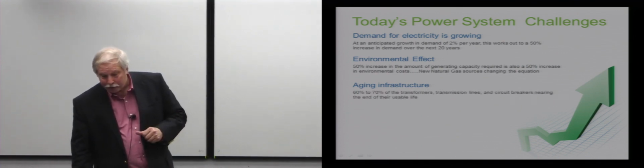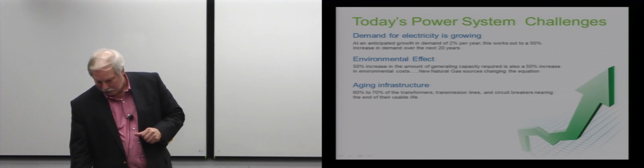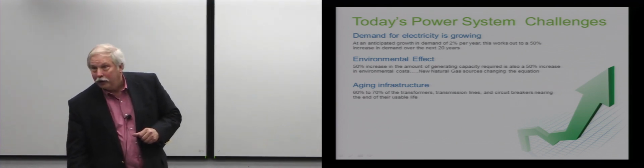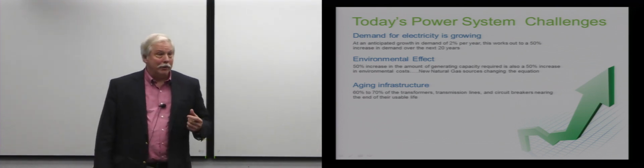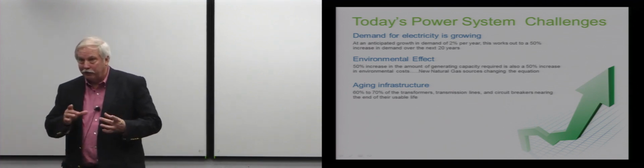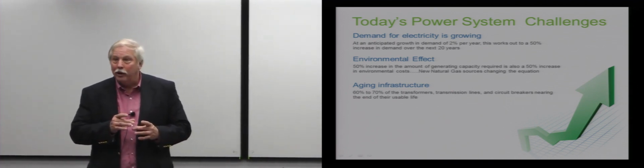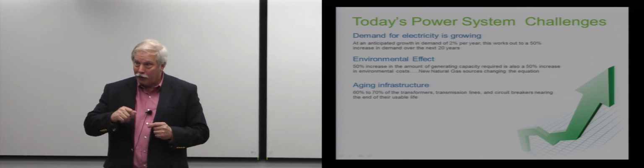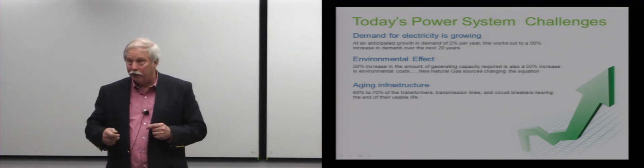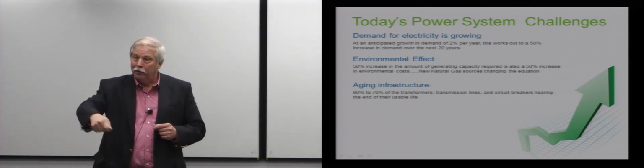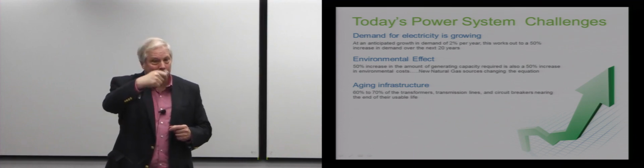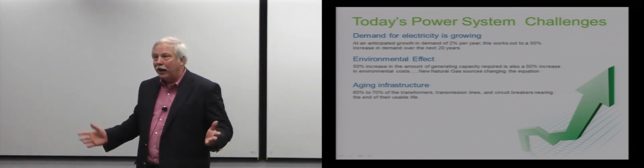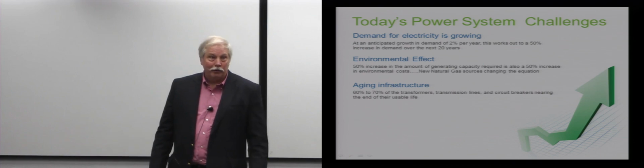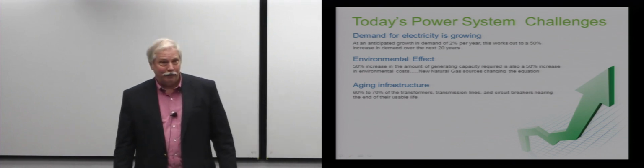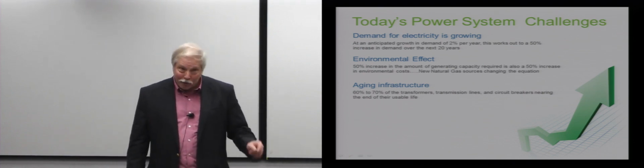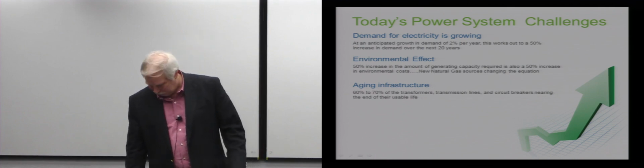60 to 70% of the transformers in this country are old. Transformers fail because of age. There's simple deterioration of insulation. All of the transformers built 30, 40 years ago are paper wound. Paper is cellulose-based, and cellulose decays over time. So they're all ticking time bombs, just waiting to explode, and unfortunately, a lot of them do.